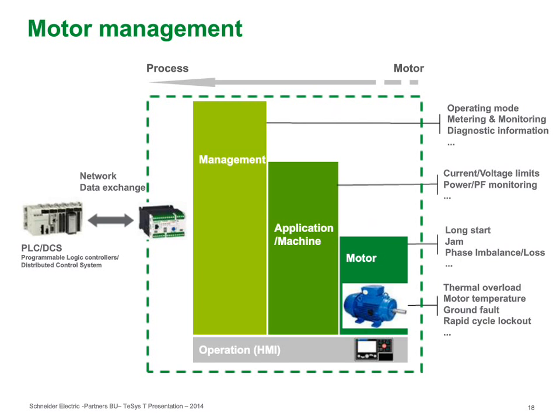Plus it can give you information if there is a fault. What kind of fault is it? Is it a long start fault? Is it a jam motor? Or is it a phase loss or a phase imbalance? But the next level is the management of your application or your machinery, taking data from the unit beyond the solid state overload relay and looking at measurements like current, voltage, and power over time, actually being energy, so it will do energy metering. And it will also monitor power factor. So if you have power factor or even harmonic issues, you can detect it through this unit.